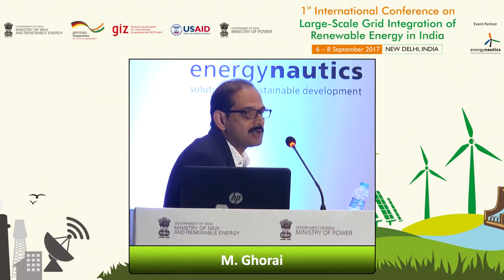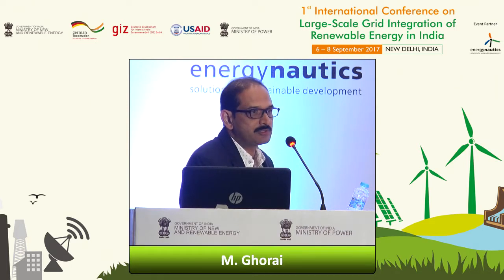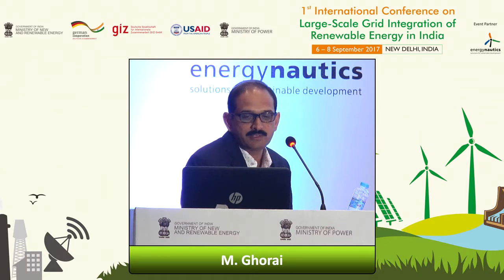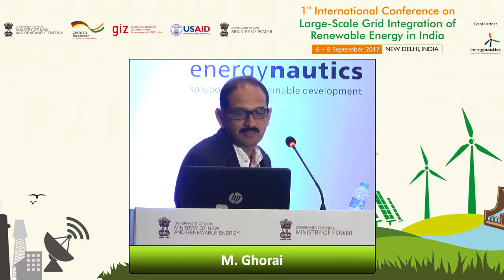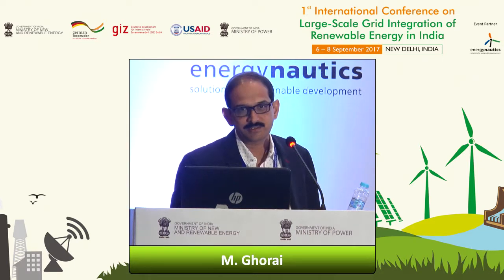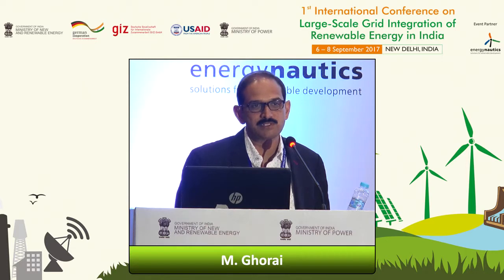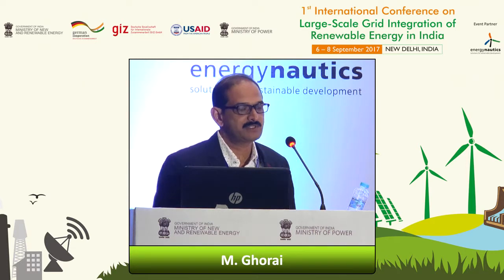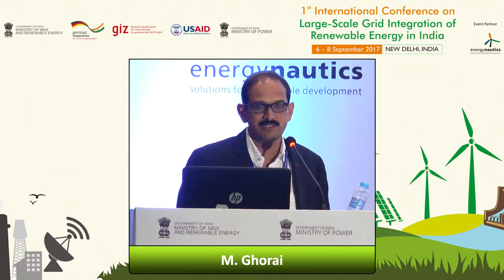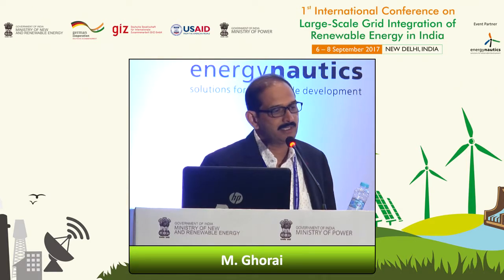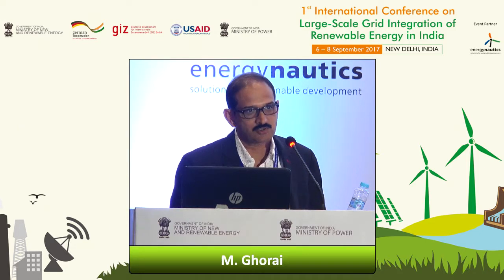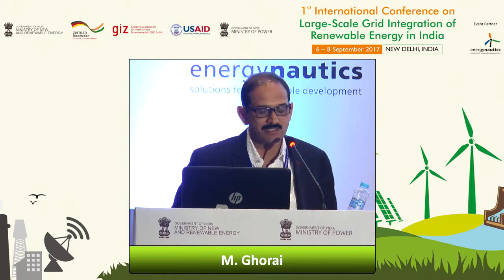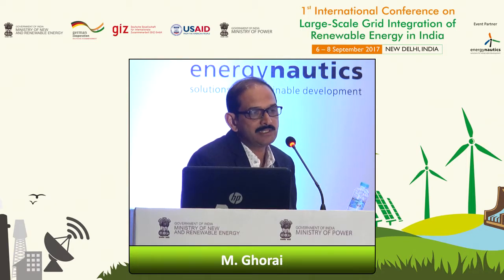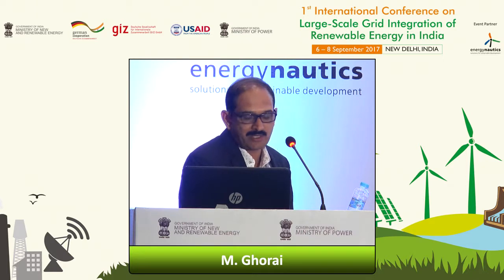So at AMSC, we have a STATCOM which we have used, as I was telling you, in more than 100 projects. This is a modular STATCOM. It's a 4 megawatt STATCOM, which we call the D-VAR STATCOM, and it's a 4 megawatt module which has 3 times overload, which means for a very short period it can give 12 megawatts, plus or minus, leading and lagging. We also have a control cabinet which can seamlessly switch other devices, so it can pull in the resources when required.